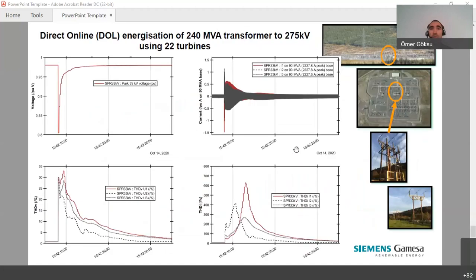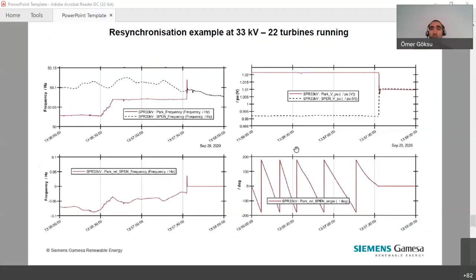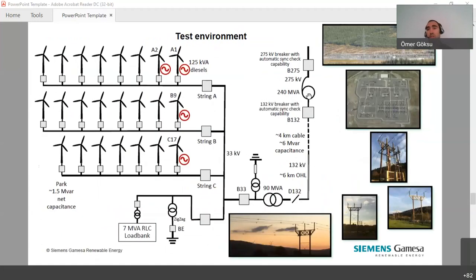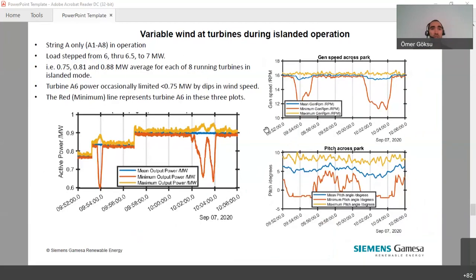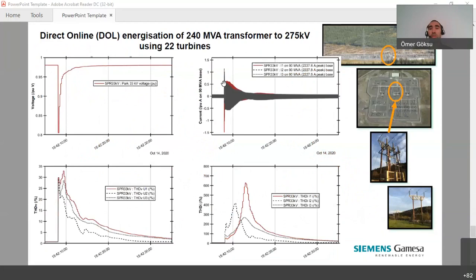And another interesting test done here, actually part of a black start, I would say personally, is the energization of the 200 MVA transformer. Let me go back to the network again. The 200 MVA transformer was being energized while it is disconnected from the main grid. So the 22 turbines were running again, and the transformer was energized. You can see the inrush, and since it's almost the whole wind farm running, the current at 33 kV, you can see here, reaches 1 per unit, and voltage was dropping transiently, which can be acceptable, but depending on who is connected. And here you can also see the transient, the decaying content of the current and voltage, the THD, sorry.